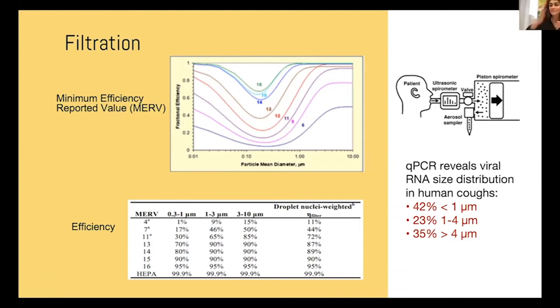So again, above 0.3 micron, very efficient. Below 0.1 micron, very efficient. So the particle size of most interest is between 0.3 micron and 5 micron. And what I told you before is 60% of the virus RNA is above 1 micron. And if you follow with me, a MERV-13, that we know we can put in our buildings, that's readily available, that has third-party efficiency testing, there is an established ASHRAE test and also international tests like ISO for a long time, actually works and works very well.